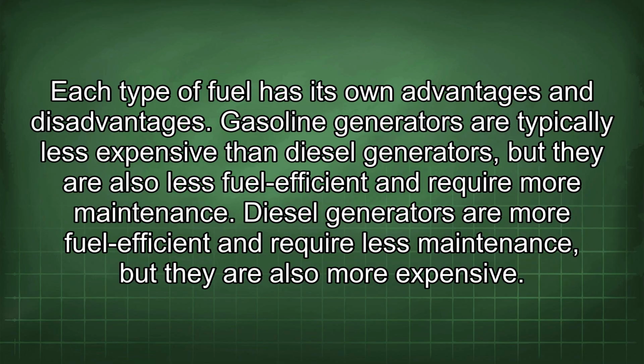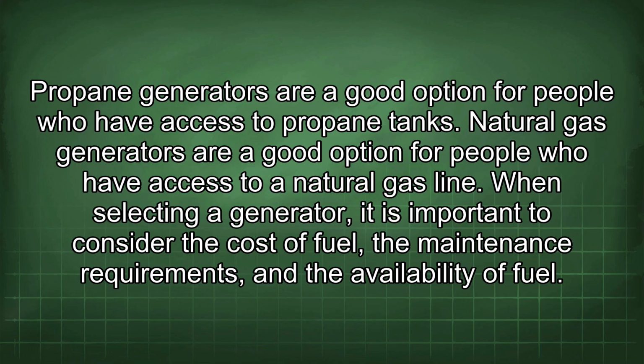Each type of fuel has its own advantages and disadvantages. Gasoline generators are typically less expensive than diesel generators, but they are also less fuel efficient and require more maintenance. Diesel generators are more fuel efficient and require less maintenance, but they are also more expensive. Propane generators are a good option for people who have access to propane tanks. Natural gas generators are a good option for people who have access to a natural gas line.